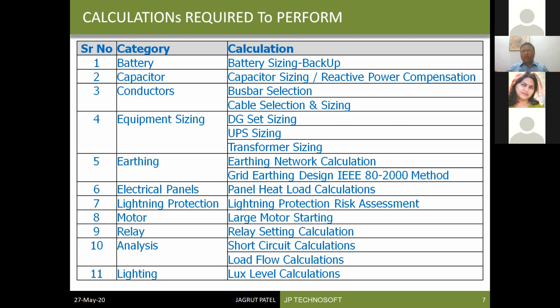Earthing is the most vital part in our system, so earthing network calculation is required. When we are working for the substations, grid earthing network design is required. Then electrical panels are nowadays widely used for any LT and HT installations, so for them, panel heat load calculations are a must. Lightning protection is a system which needs to be employed for any kind of buildings nowadays. It is being made mandatory by the Government of India through various standards. So lightning protection risk assessment is again a calculation which needs to be performed.